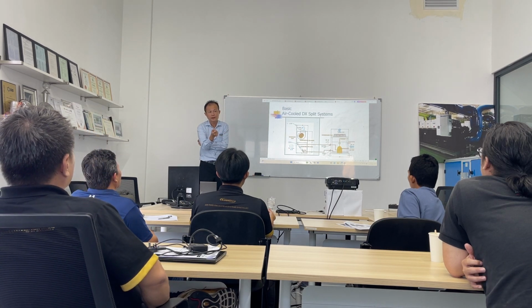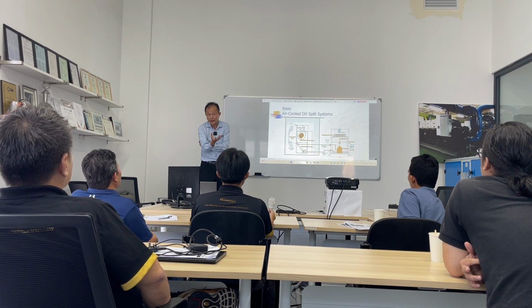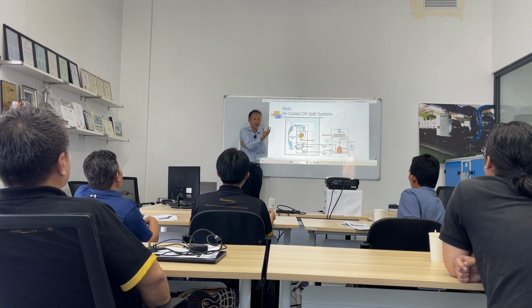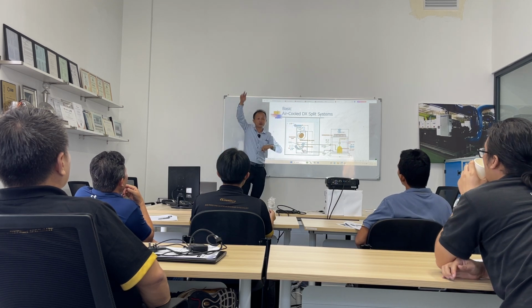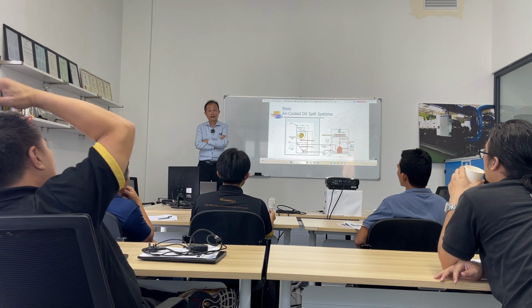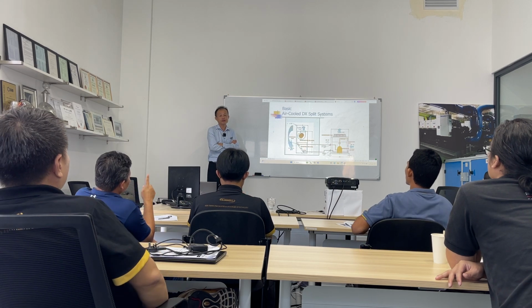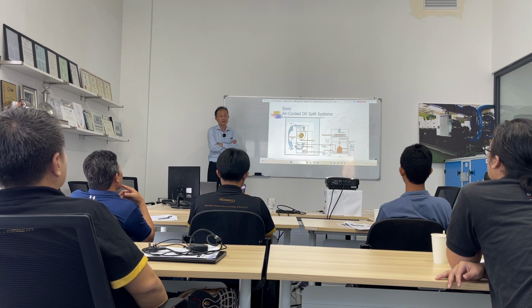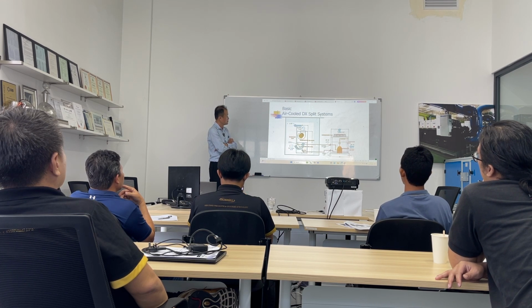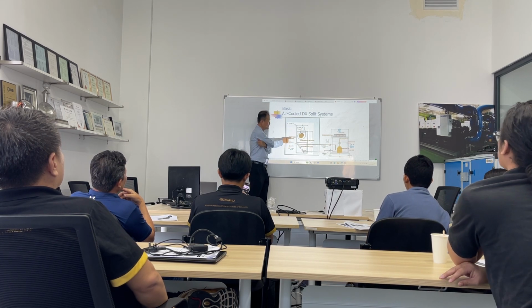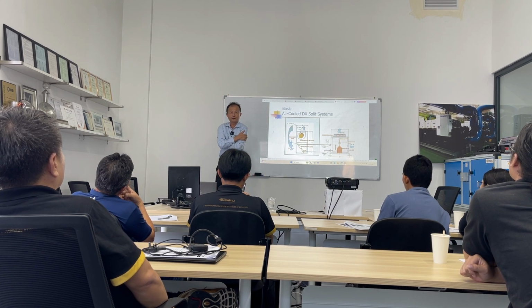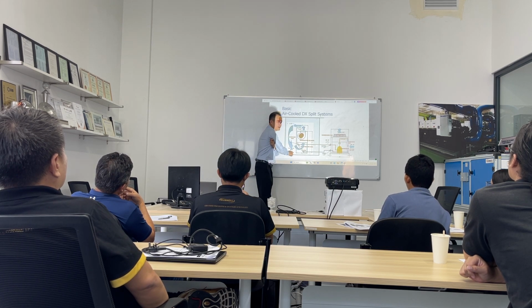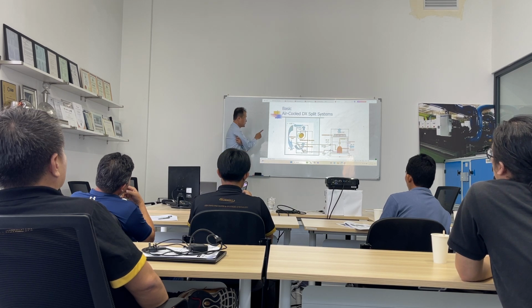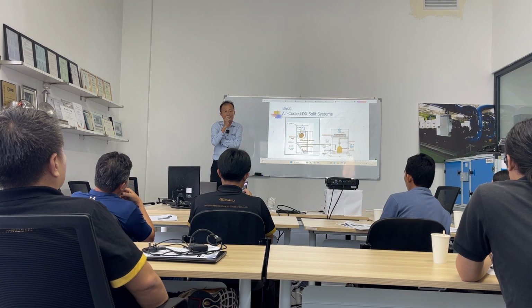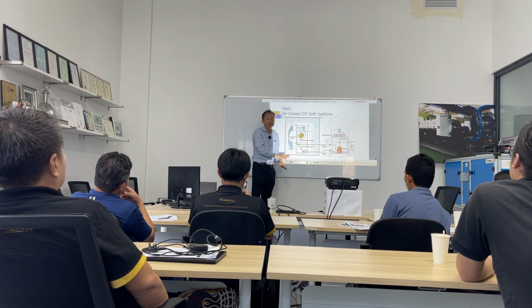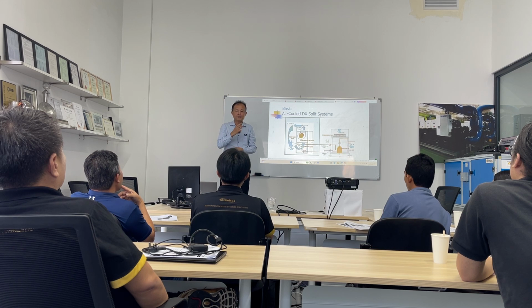Yes, that is what? Room temperature, but this is, I know, dry bulb, right? Okay. So if I tell you that now the room RH is 55%, for example, what will be the likely wet bulb temperature that you need to determine? Now, let's say that without the outside air, the dry bulb temperature is 75 degrees F. I agree with you. That is the on-coil temperature. That means that is the temperature that you enter the coil, and this is dry bulb.